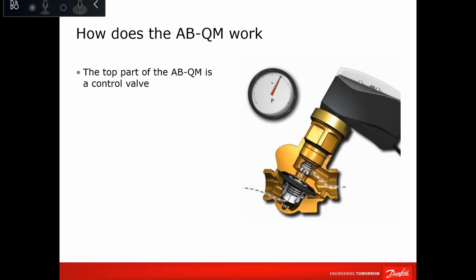So yes, it's what you need in order to define your critical point, your differential pressure transmitter location and set point. This will be used to control your pump, ramping up and ramping down. And you need that in order to minimize any excess of flow, even with PICVs. We know that 100% will never be exceeded by a PICV, but less than that, if you would be able to run your system at 30% and you are running it at 50% due to a wrong location of the DP sensor, then this calculation might help.